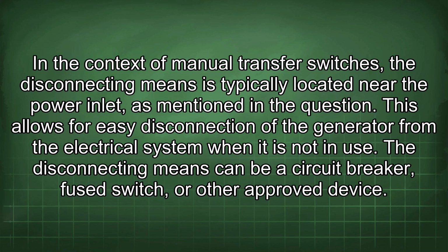In the context of manual transfer switches, the disconnecting means is typically located near the power inlet as mentioned in the question. This allows for easy disconnection of the generator from the electrical system when it is not in use. The disconnecting means can be a circuit breaker, fused switch, or other approved device.